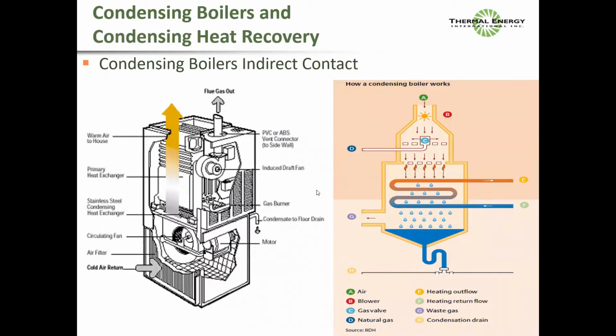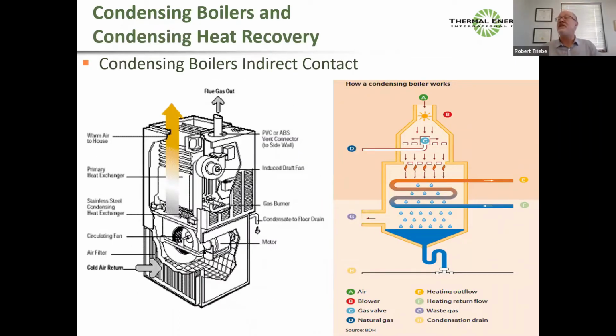So now I'm just going to look at the technologies quickly before we discuss integration. So again, the two terms that are key are direct and indirect, which means that the hot and cold sides either are in direct contact or they're heating through a tube or a wall. We're talking about boilers and economizers. So here we go, 4 categories. First, condensing indirect contact. I don't even like calling them boilers. They don't boil a damn thing. So it really frustrates me that the whole hydronic world still calls them boilers, but they do, so I'll still call them boilers.